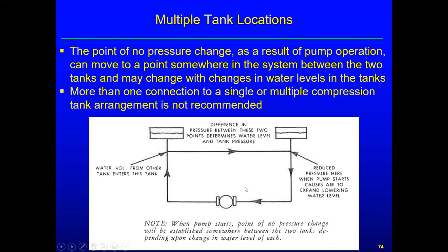The point of no pressure change as a result of pump operation can move to a point somewhere in the system between two tanks and may change with changes in water level in the tanks. More than one connection to a single or multiple compression tank arrangement is not recommended. We don't want to do this.